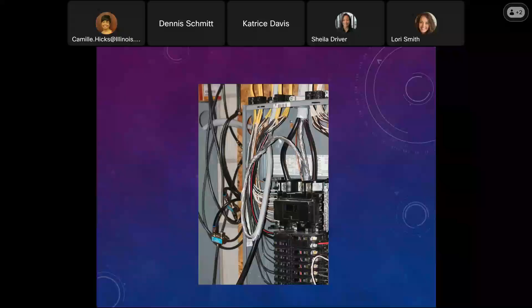Electrical panels, there's a couple violations here. One, there's no cover on the electrical panel, and two, they're feeding the wire, a main line, coming in from the face of the panel and not through the side, so they couldn't even put a panel on there if they had. So this is actually a violation because that is an unsafe area for an electrician to actually come in and do work. In an emergency, somebody's reaching for an electrical breaker to shut it off because the power is out, whatever, they could be electrocuted.